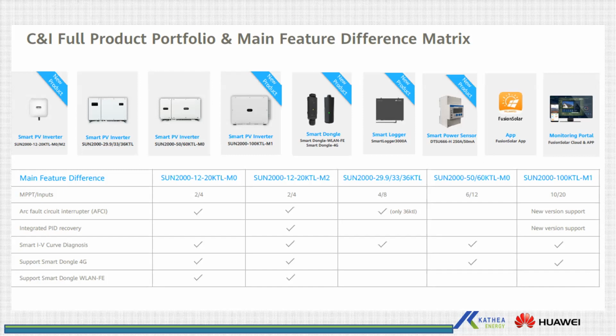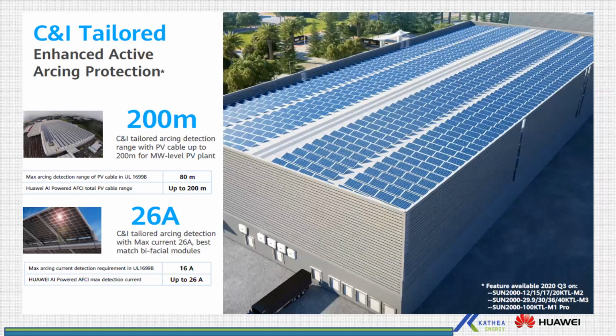And then the inverters also support the smart dongle 4G, except for the 29 to 36 range. The newer version, also coming in Q2, will be able to support the smart dongle 4G. And then for the WLAN dongle, which is the WLAN fast Ethernet, it's only supported by the lower range C&I, which is the 12 to 20. So for the 29 and above, if your internet source is Ethernet, then you need to use a smart logger on the system. As I have said, our inverters have built-in arc protection.